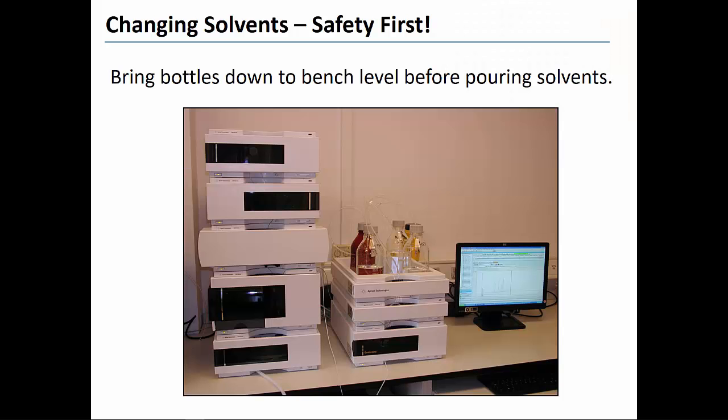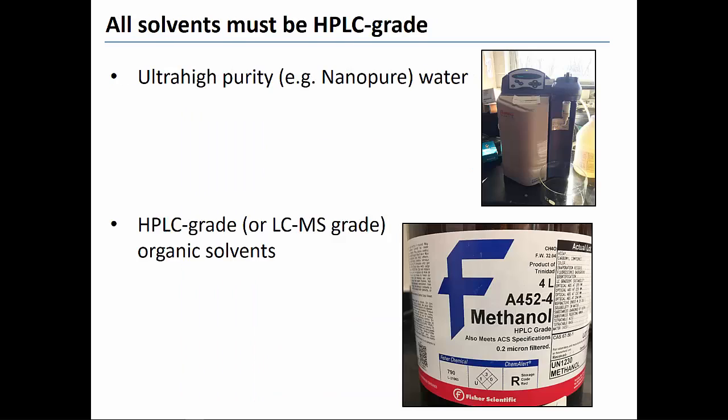For your safety and the safety of the instrument, remove solvent bottles from their typical position above the pumps and set them on a lab bench away from the instrument and away from computers when pouring solvents. All solvents used for HPLC analyses must be HPLC grade. Water must be obtained from a water polisher, such as the NanoPure system shown. All organic solvents must be labeled as either HPLC grade or LCMS grade.